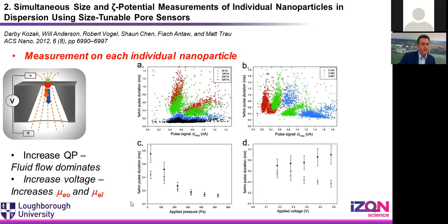And what I'm showing in the data, just to underline, and I think it is an interesting point, is that if you increase the applied pressure, what they've got in this paper are two particles, so I'm going to circle them here. They have what they termed a high charge and a low charge particle. At low pressures, you can see that the high charge and the low charge particle have very clear differences in their particle velocities. And as you increase the applied pressure, those velocities converge. So you can dominate the flow, you can dominate the speed of the particle by the pressure and eliminate the effects of the electrophoretic speed. So it's something to consider when you're optimizing your parameters for your measurements, to make sure that you haven't had to apply too big a pressure from the system.